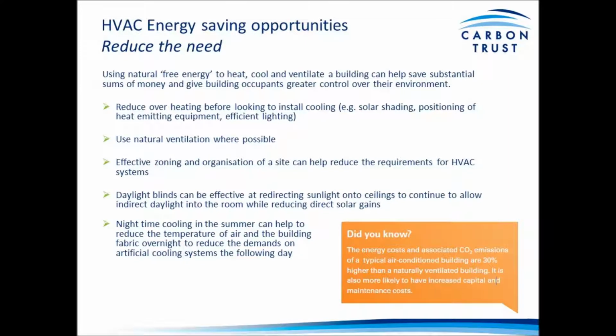So one way of reducing your energy consumption with the HVAC systems is to reduce the need. And before we look at how we do that with individual systems, considering the HVAC system as a whole, you can make quite simple improvements before looking to invest. So you can reduce overheating and the requirement for cooling with effective shading, so positioning heat emitting equipment such as printers in separate rooms, and have highly efficient LED lighting, which gives off much less heat than standard fluorescence, again reducing your cooling demand. You can open windows as discussed before switching on cooling.